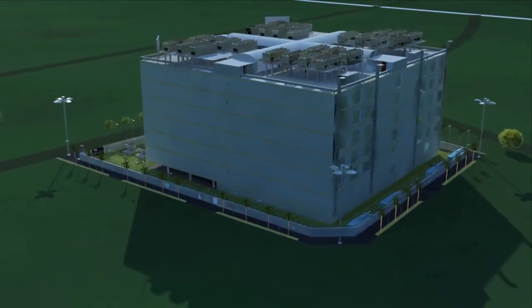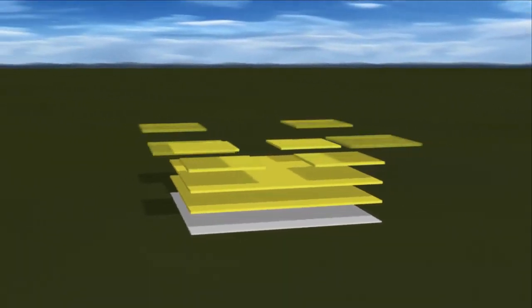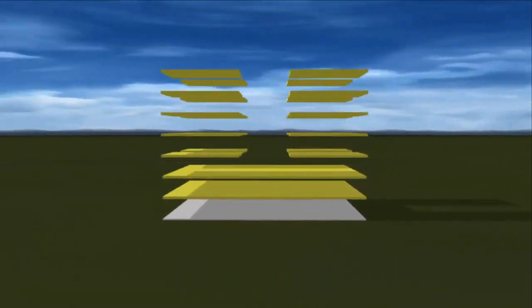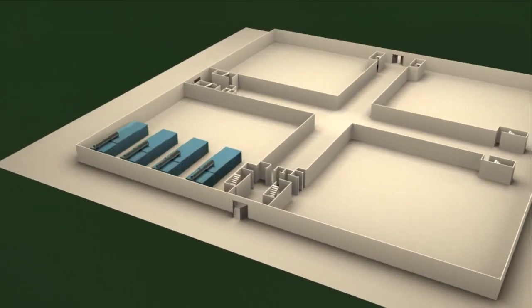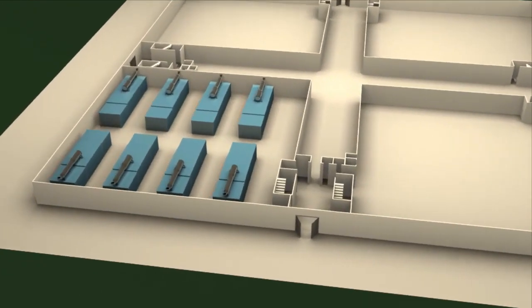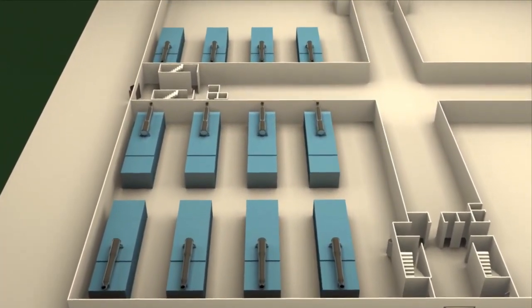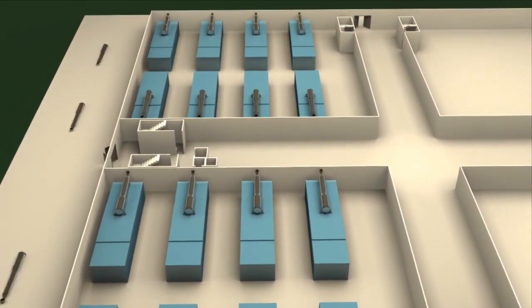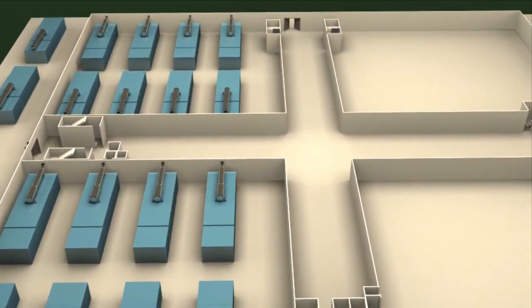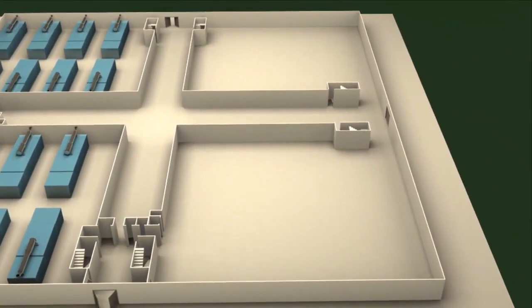The building is a seven-level structure including two base floors that house the utilities and office area. The ground and first floor covers the complete area of the building. The ground floor houses 16 generators of 4 megawatt capacity each. A foolproof dry powder anti-fire system ensures any possible fire hazard is addressed. In addition, four generators are placed on the setback. Two complete floor plates of 25,000 square feet each are set aside as staging areas for equipment for future build of the data center.